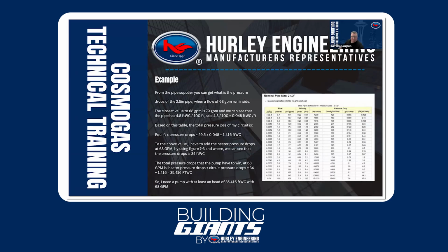So where we started off at 33, 33.5 feet of head loss to our heat exchanger, now our total system head loss is up to almost 35.5 feet of head loss. So when this comes into play is when you're sizing pumps and you're right on the line and you're curious, then you need to take into account what's my head loss through this piping at the required velocity that I need. Otherwise, you could potentially undersize your pump.